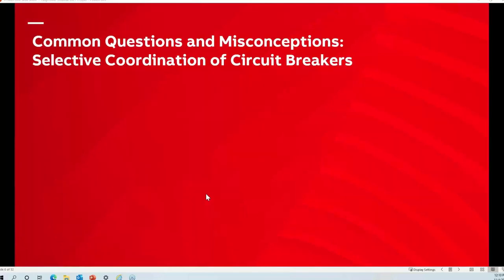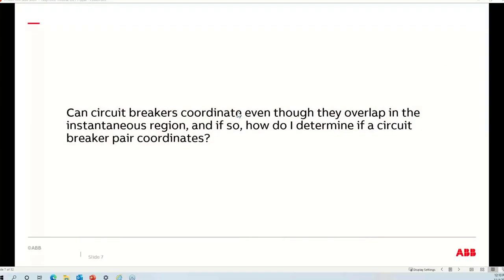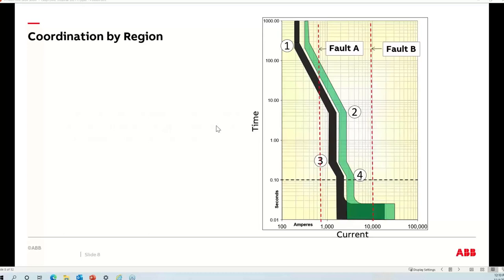With that quick background, let me jump into the various common questions and, in some cases, misconceptions. Selective coordination of circuit breakers — most folks in design and typical commercial or institutional systems know circuit breakers can coordinate. But if you haven't done that type of work, you may see overlapping time-current curves and wonder: how can those possibly coordinate if they're overlapping? Can circuit breakers coordinate even though they overlap in the instantaneous region, and if so, how do I determine if a circuit breaker pair coordinates? The answer is yes, but let's work through it.